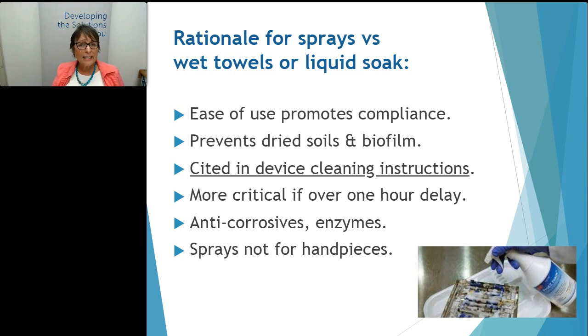The other thing I would like to mention is that there are some devices that should not be sprayed. They might be wiped off, but they shouldn't be sprayed. And those would be electronic devices, typically also powered devices like dental handpieces. And of course, as always, look in the device IFUs, the instructions, to find out what the manufacturer recommends.